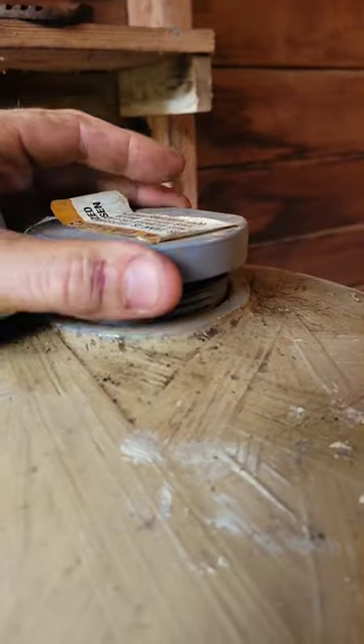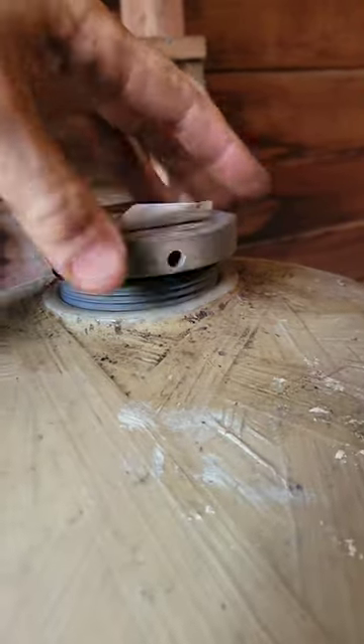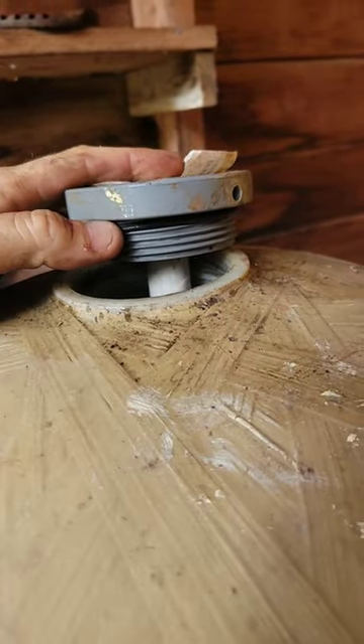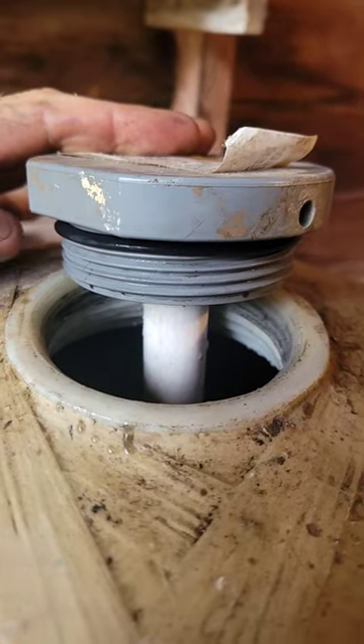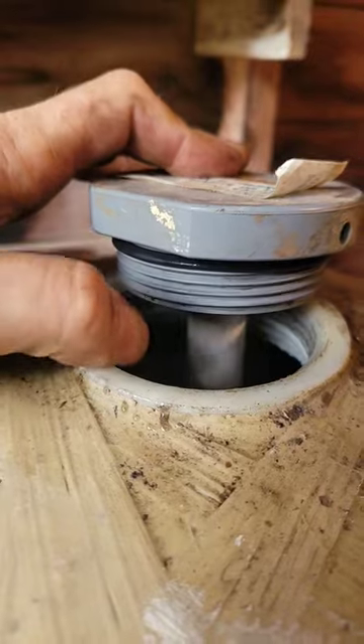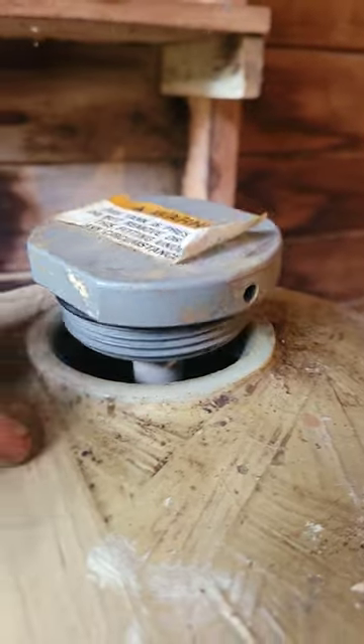I noticed when I got here the top was loose — so loose that I just unscrewed it by hand. I inspected the o-ring and it looks like it might have been leaking. A lot of times you can fix these o-rings by just flipping them over and getting a new resealing surface on the threads here. There's not really a groove for the o-ring to sit in.